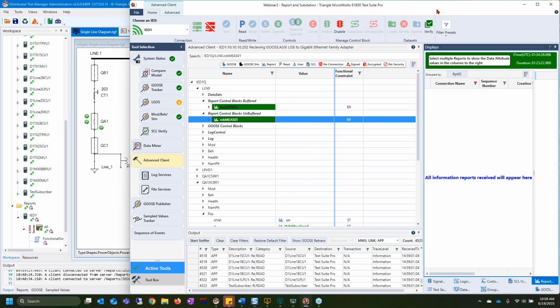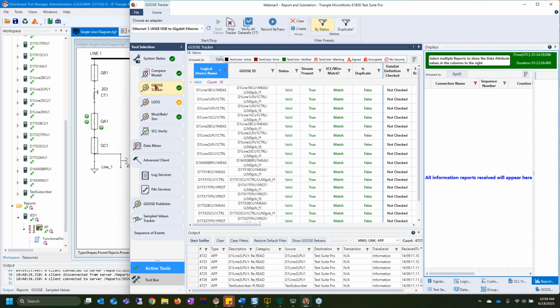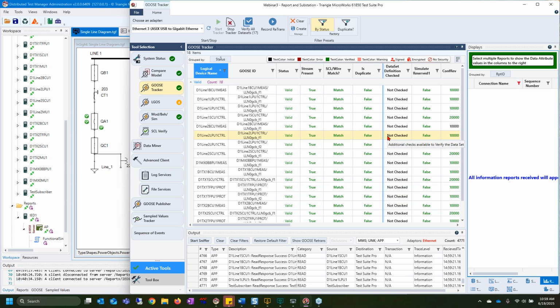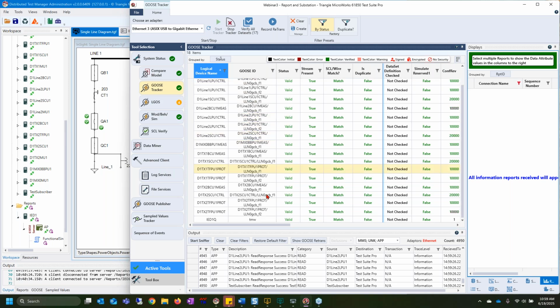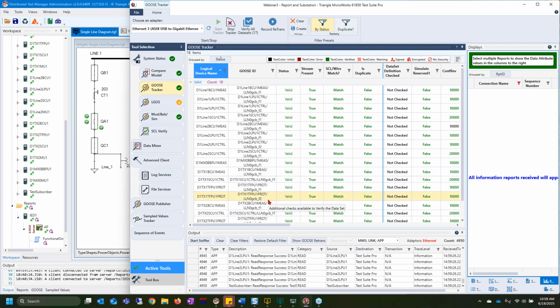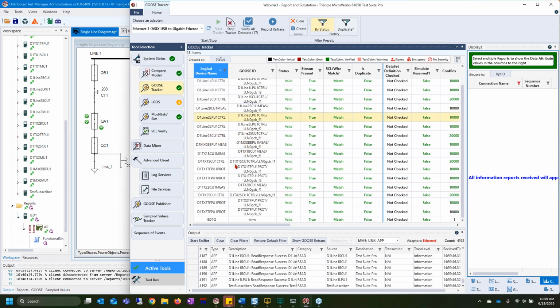So how, as GOOSE is normally peer-to-peer or server-to-server communication, can we use a testing tool and a diagnostic tool like Test Suite Pro to monitor what's going on? Well, the first thing that we can do is take a look at the GOOSE tracker. The GOOSE tracker is just a combination of every file that you provided to TSP and all of the relevant GOOSE streams that are expected to be there. It will also let you know if there's any rogue or undefined GOOSE messages, GOOSE streams on the wire that it is seeing. So you select your adapter, whatever is going to the switch where the GOOSE is going to be distributed at, and then you'll be able to see, currently I have 18 different streams of GOOSE messages coming through.